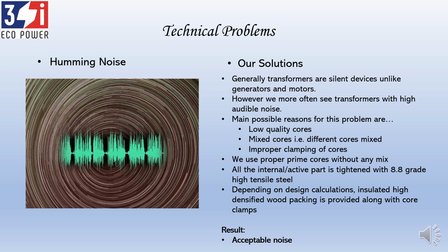Another reason is not clamping the core and coil properly. If you are not doing that, the cores become slightly loose and generate more noise. We contain that by proper clamping with wooden blocks, and by using high tensile 8.8 grade steel. So once tightened, it will stay tightened forever. One important case study which I feel is worth mentioning here: once you tighten the core and coil assembly in a transformer and lower it into the tank, the tightness should last a lifetime.